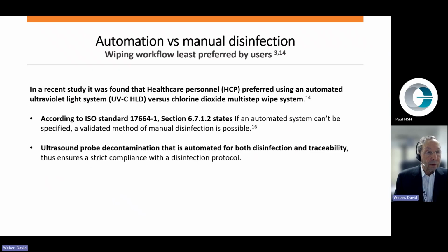In a recent study, it was found that healthcare personnel preferred using an automated ultraviolet light system, UVC, high-level disinfection, versus chlorine dioxide multi-step wipe system. According to ISO standard 17664-1, section 6.7.1.2 states, if an automated system can't be specified, a validated method of manual disinfection is possible. Ultrasound probe decontamination that is automated for both disinfection and traceability thus ensures strict compliance with the disinfection protocol.